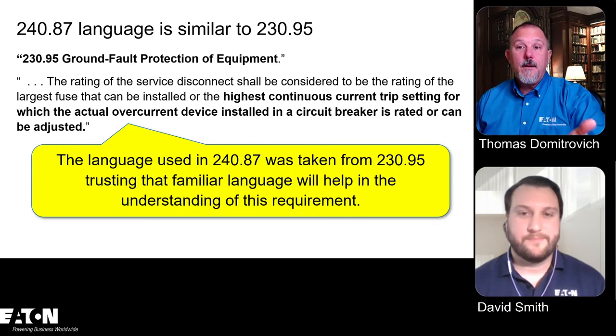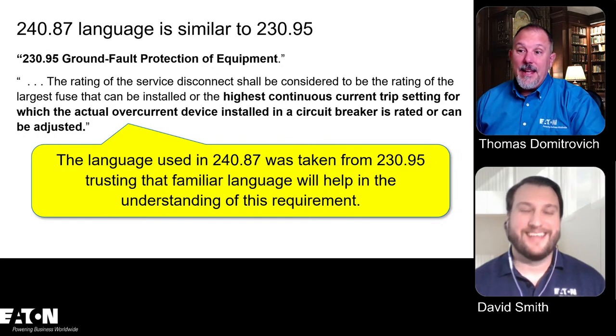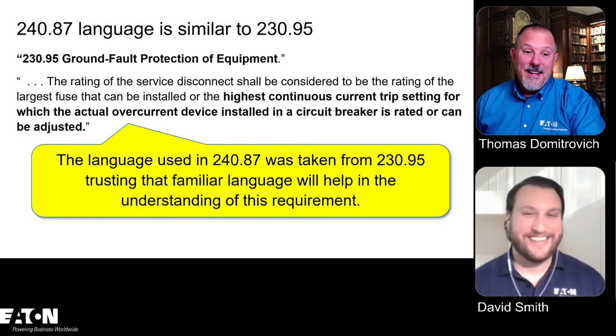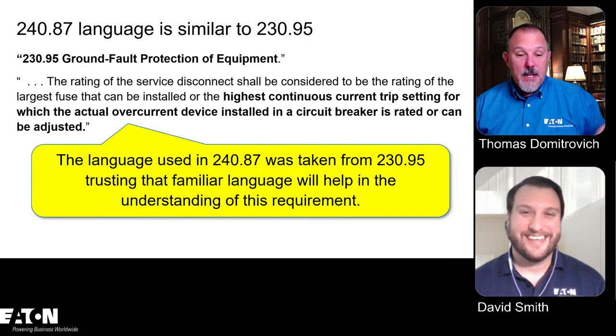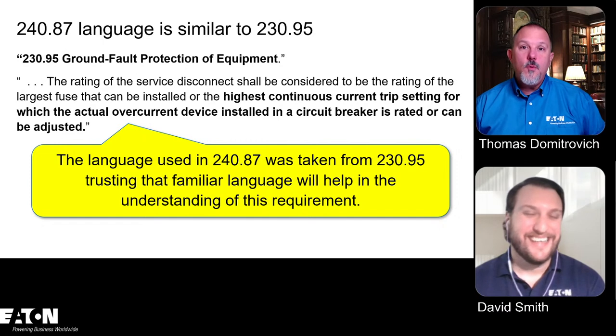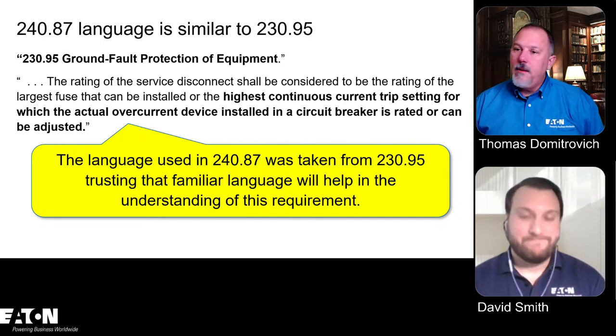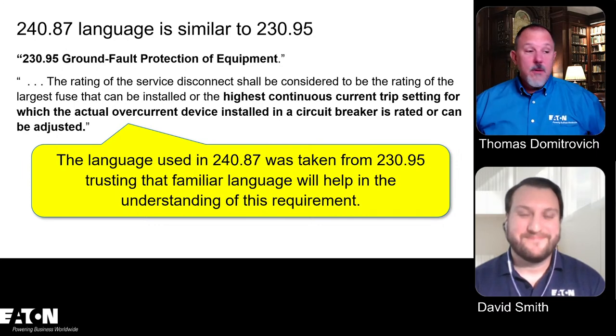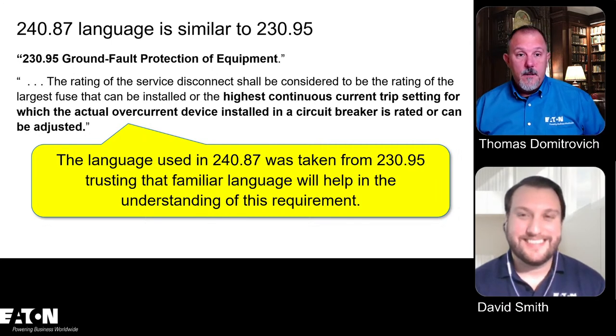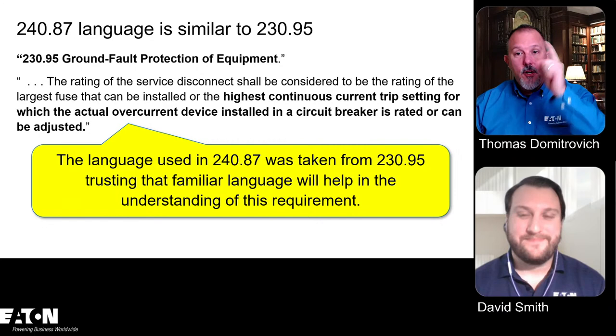Now, the power breaker, I call it the double wide, is the only one without an instantaneous. And that's what I told Jimmy and others. I said, look, 240.87 only applies to the double wide. And you rarely see those in a power system because it's literally a double wide. They're two breakers side by side built as one because they separate the current into all these different contacts to make it easier to interrupt, to hold those contacts closed. They separate the energy like Napoleon, divide and conquer. And we hardly ever sell those because they're so expensive. That's right. So that's when they said, you know what, we're going to go to this language.